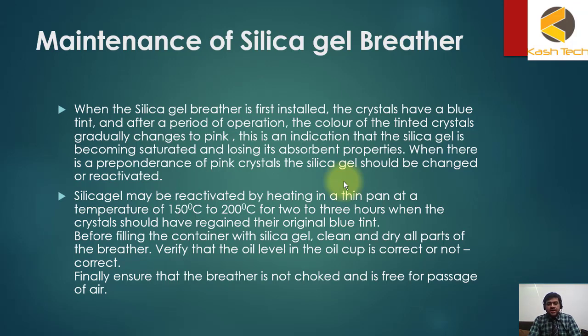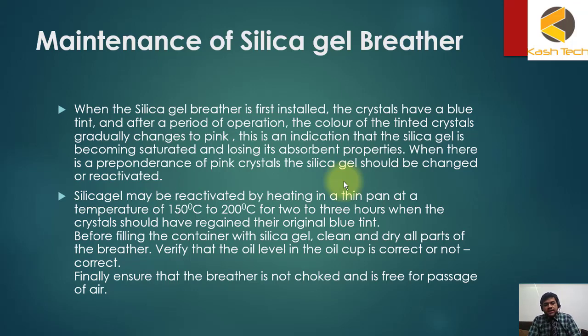Silica gel may be reactivated by heating in a thin pan at a temperature of 150 to 200 degrees centigrade for two to three hours, after which the crystals should regain their blue tint. Before refilling the container, clean and dry all parts of the breather, verify the oil level in the oil cup is correct, and ensure the breather is not blocked and is free for passage of air.